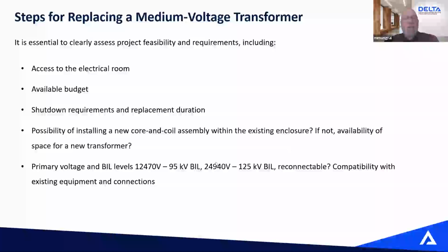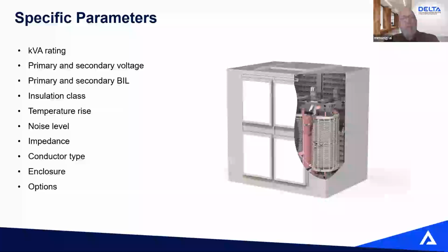And in some markets, like Montreal and Vancouver, the feed will eventually upgrade to 25 kV. Right now, it's at 12,470. So are we considering a dual wound primary transformer, so that when the utility changes the voltage, we will be up to pace with the new regulation? We need to consider many criteria when we replace a transformer.